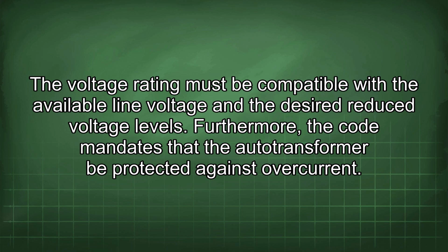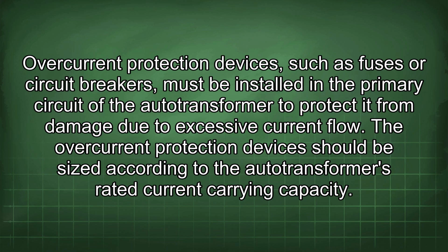Furthermore, the code mandates that the autotransformer be protected against overcurrent. Overcurrent protection devices, such as fuses or circuit breakers, must be installed in the primary circuit of the autotransformer to protect it from damage due to excessive current flow. The overcurrent protection devices should be sized according to the autotransformer's rated current carrying capacity.